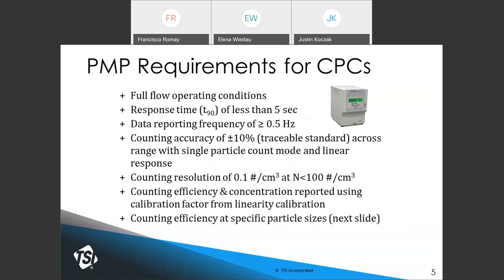This CPC has very specific requirements. Most importantly, it needs to be a full flow CPC with a response time of less than five seconds, counting accuracy of plus or minus 10% with respect to a traceable particle number standard, and a counting resolution of 0.1 particles per cc. The CPC may also report a counting efficiency and concentration with a calibration factor. CPCs have specific requirements for counting efficiency at different sizes.